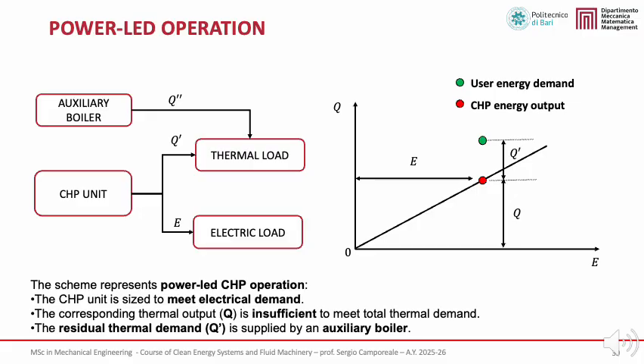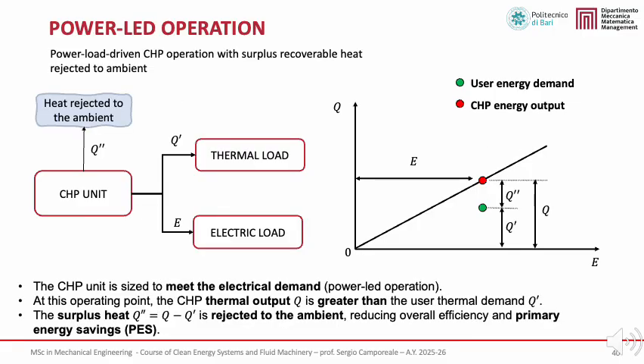thermal output. In this slide, we consider a specific power-led CHP operating condition in which part of the recoverable heat cannot be utilized and is therefore rejected to the environment. As in all power-led configurations, the CHP unit is sized to meet the user's electrical demand, and the electrical load determines the operating point of the system. At this operating point, the corresponding thermal output of the CHP unit is greater than the user's thermal demand.